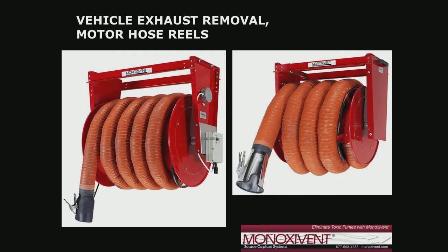But in this instance, there's an overhead crane. And the overhead crane travels back and forth just underneath the hose reels. So if I had my spring hose reels there, and because I need enough hose hanging down for an average sized man or woman to be able to reach it, that hose would impede the travel of the crane. So in this particular scenario, we went to motorized hose reels to make sure that we could bring the hose up and out of the way of the travel of the crane.